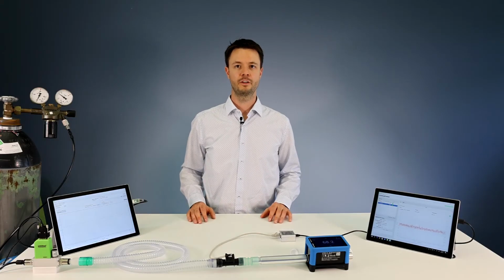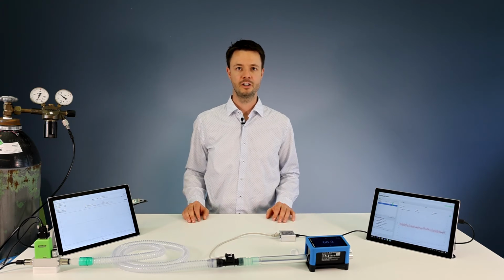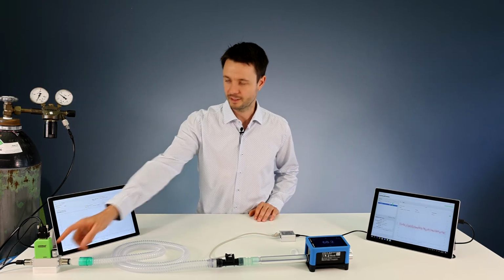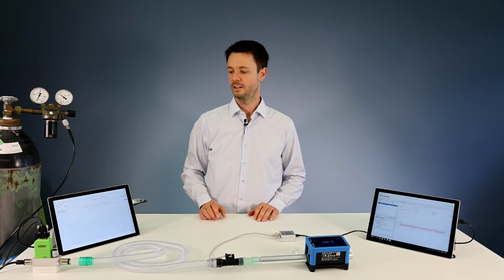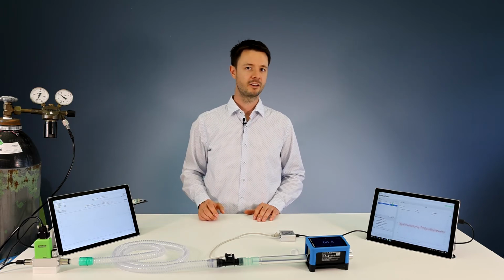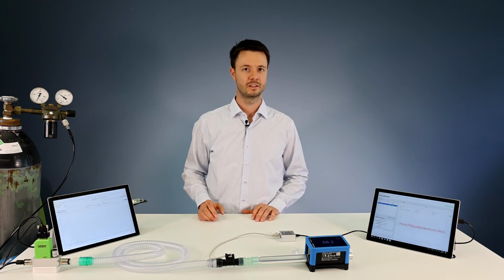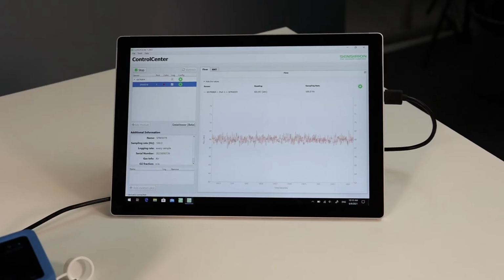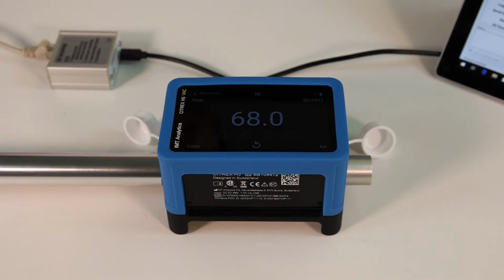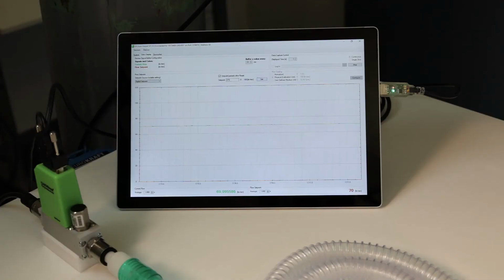The first thing we can observe, or rather hear, is the setup is very noisy, which is an indication for turbulences. Indeed, any proportional valve creates jets with lots of energy. These jets and turbulences make an accurate flow measurement very challenging. But let us see what we get. The flow sensor shows roughly 68 liters per minute, and the reference is showing us 68.0 liters per minute. Indeed, we see that both readings are deviating from the set point of 70 and are close to the lower limit of 67.2. So let us stop the measurement.